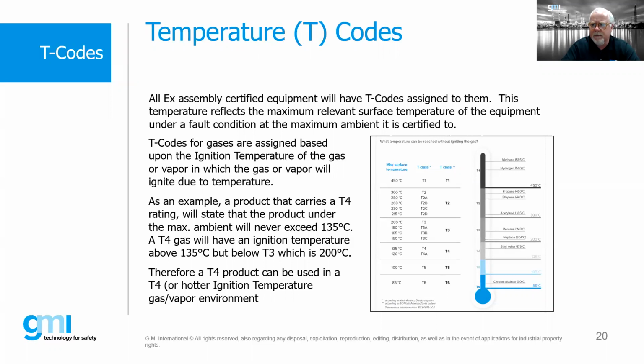What that basically means is that if we have an environment in which T6 gases are present, we have a gas there that has an ignition temperature of something between 85 degrees C and 100 degrees C. If we have a T5 environment, that means we have a gas present that's somewhere between 100 degrees C and T4, which is 135 degrees C. So using T6 as an example, which is a very, very low temperature, the only product we could use for a T6 environment is a product that has a T6 rating.